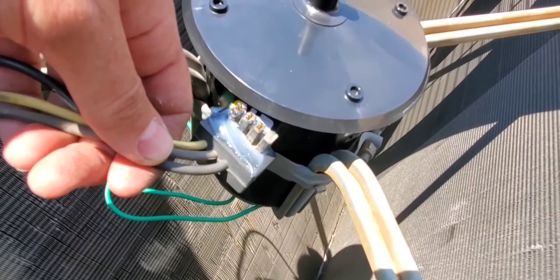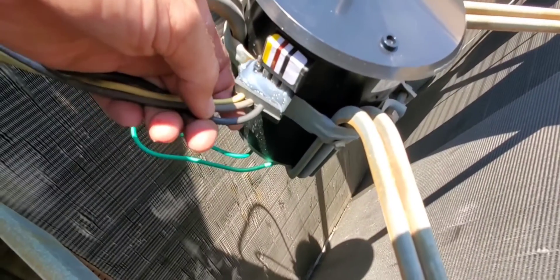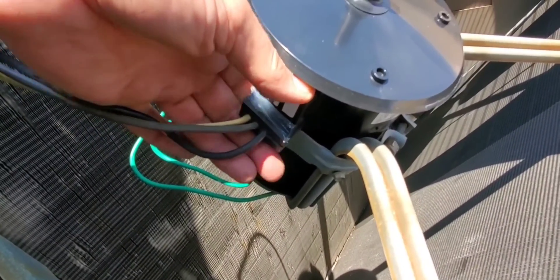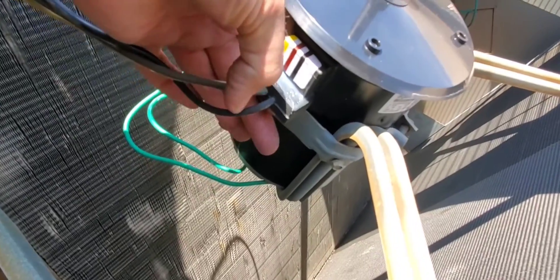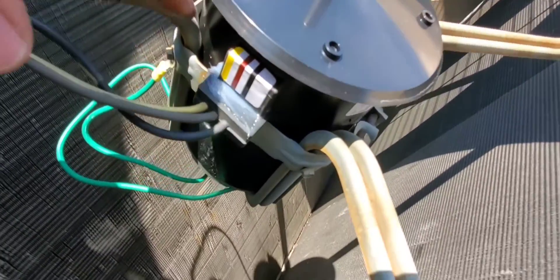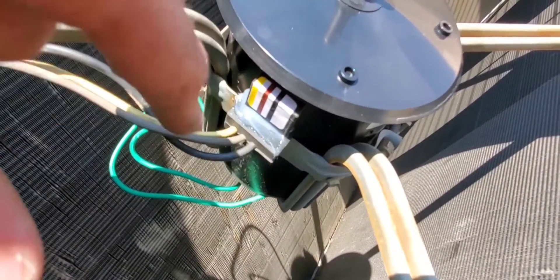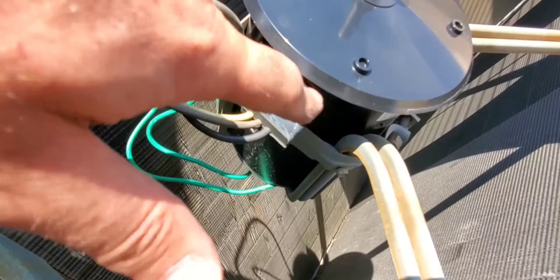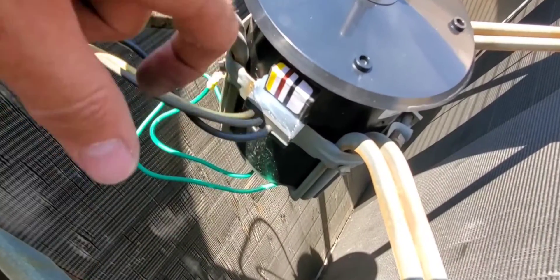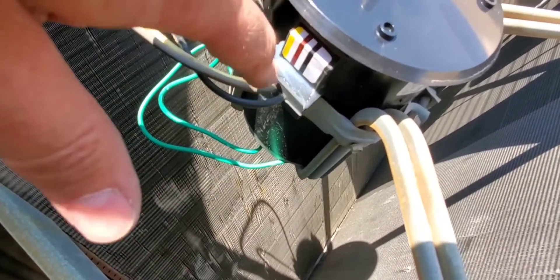So I've coated the plug on the base and then we just plug it in. Okay, and then we just take a rag and wipe away the excessive silicone grease. That will leave a moisture barrier right there. And we take a zip tie and we zip tie this connection together. And trust me, it helps prevent moisture from infiltrating this connection point.